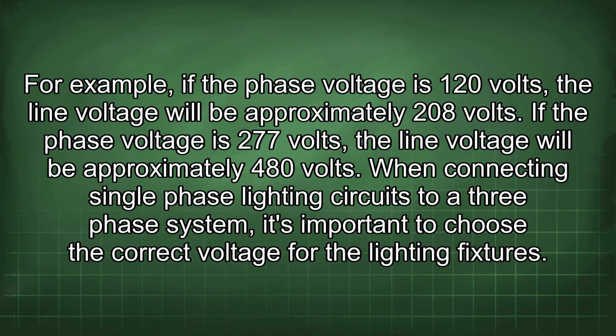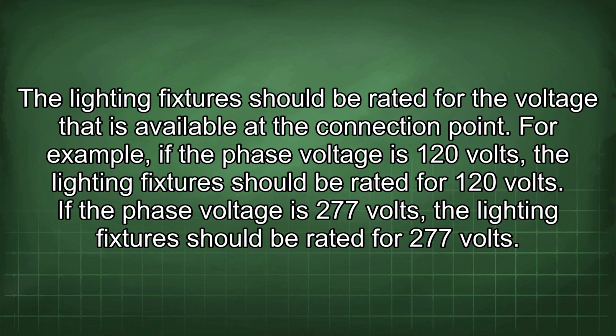When connecting single-phase lighting circuits to a three-phase system, it's important to choose the correct voltage for the lighting fixtures. The lighting fixtures should be rated for the voltage that is available at the connection point. For example, if the phase voltage is 120 volts, the lighting fixtures should be rated for 120 volts. If the phase voltage is 277 volts, the lighting fixtures should be rated for 277 volts.